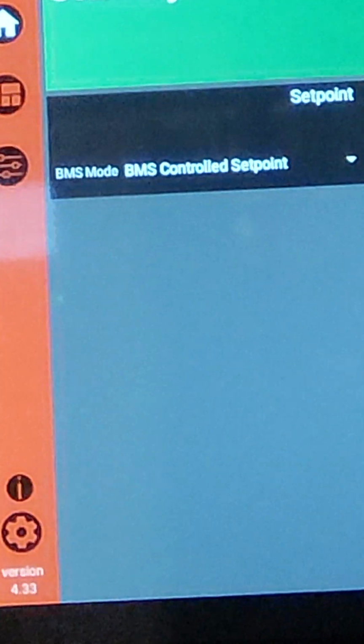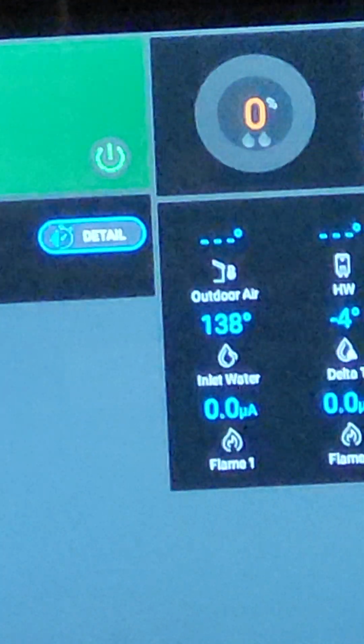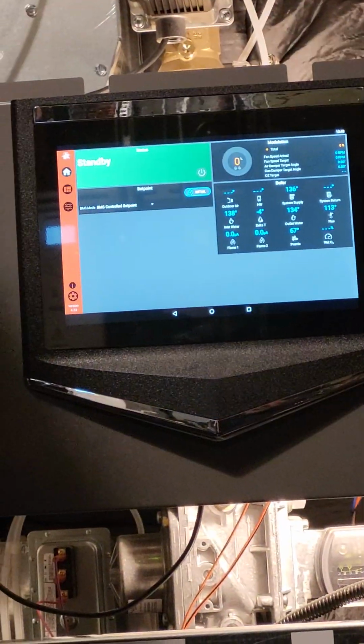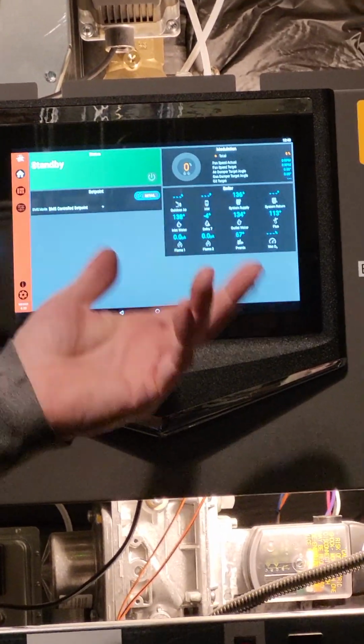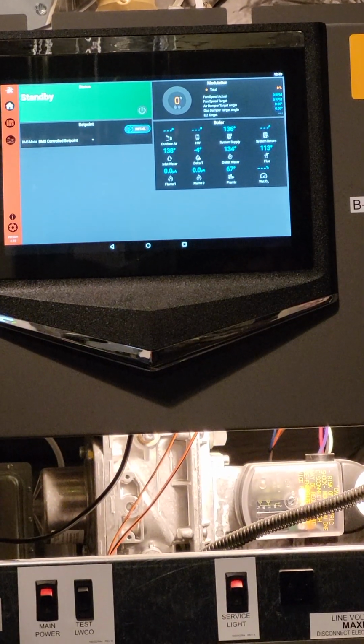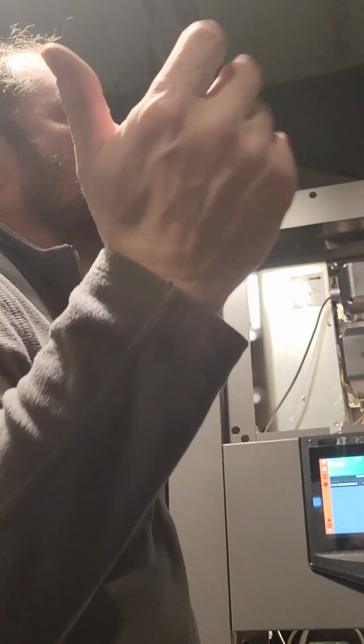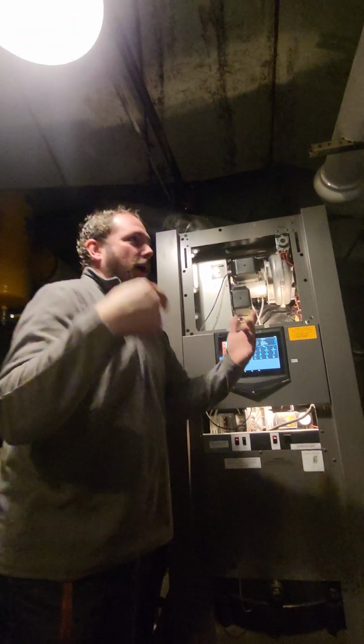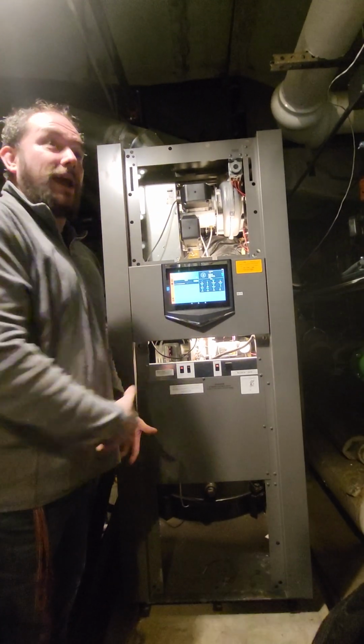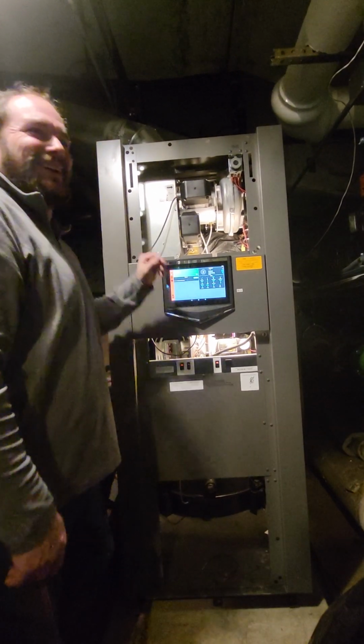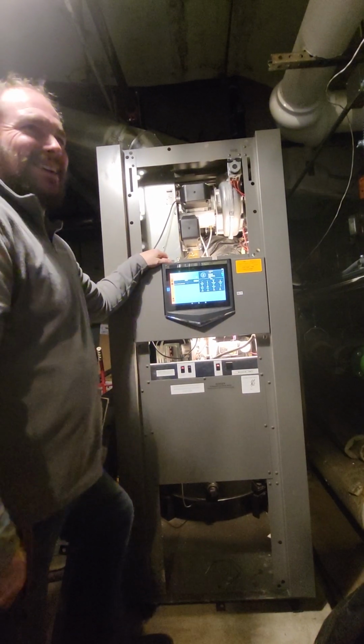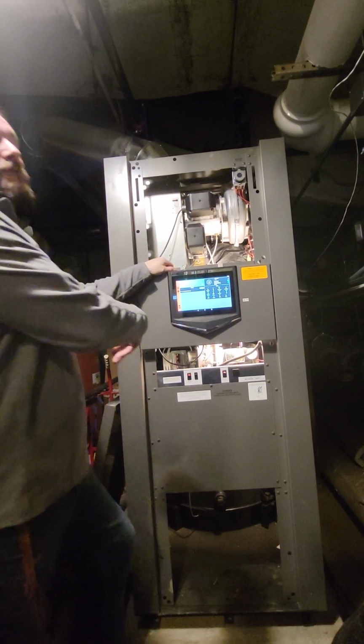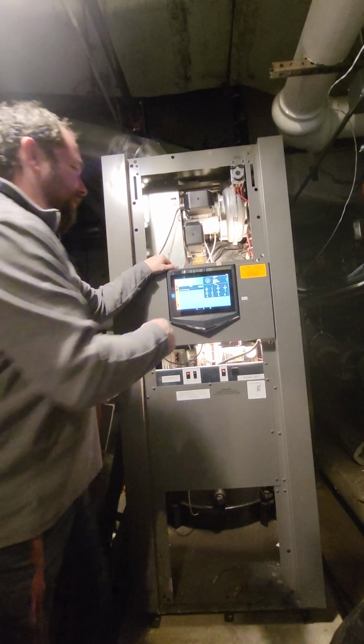If you wanted to, let's say something happened, the BMS panel went down for whatever reason, you could change that to local set point and just give it whatever local set point you want, 140, and it would just maintain 140 on that sensor if needed. So, if something of that nature ever happened, which we all know is probably extremely unlikely, there is a way to manually power it up. Not here, it's quite common. Controller just took a shit. Ah, man. Gotta go around and put everything local. You have the ability to locally control if you ever needed to.